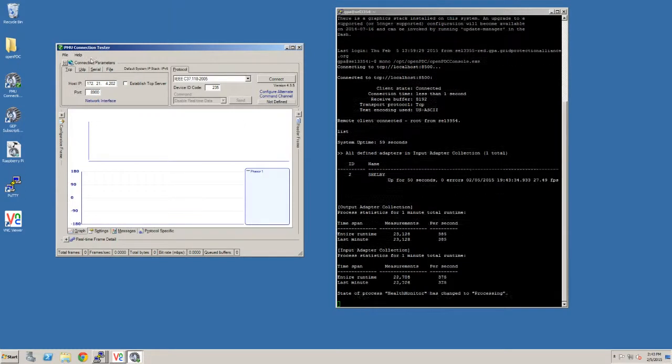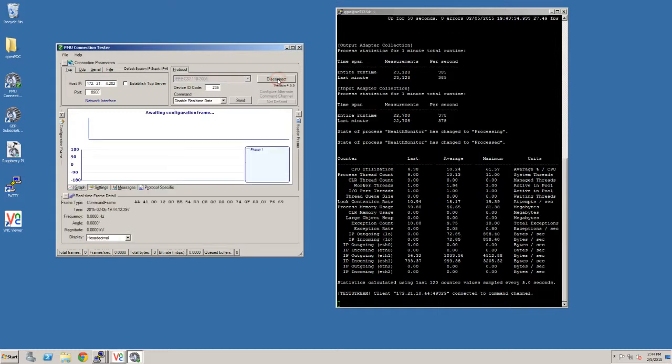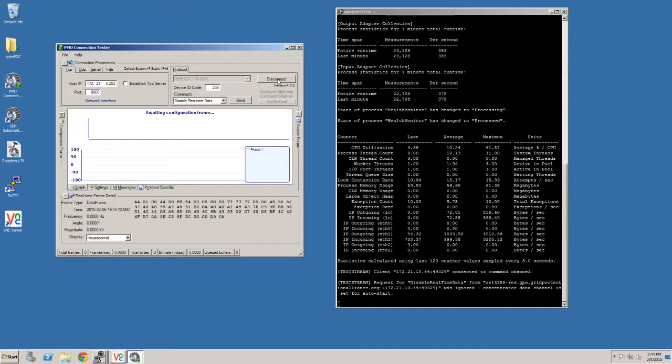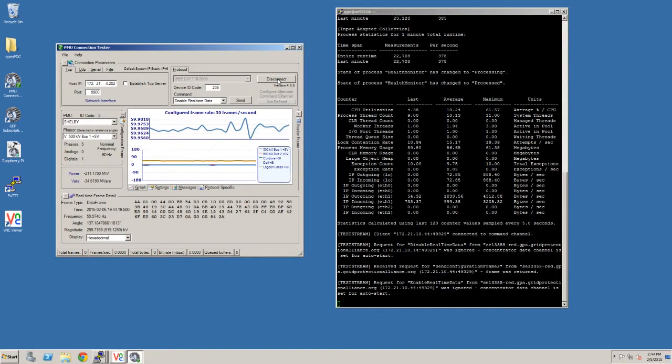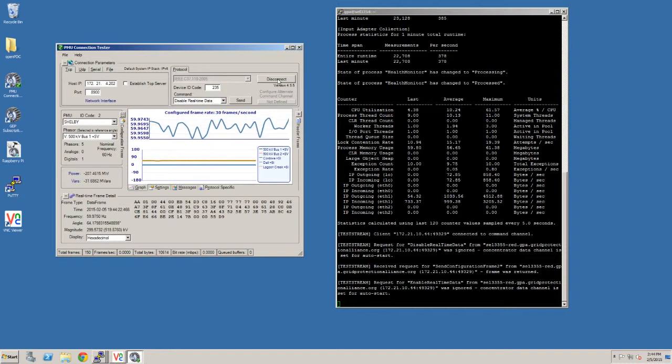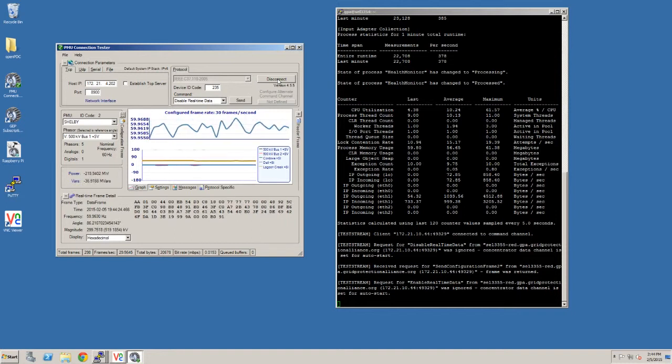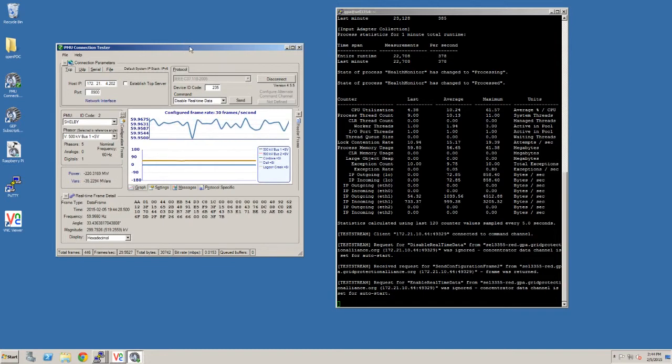Now let's try the PMU connection tester. Okay, now I'm going to type in the IP of that machine. It's actually on our right, 202. Okay, good. C37, port 8900, TCP, go. Yay, all right. So you can see on the screen how on the feedback from the open PDC, it saw a connection. And you can see that we're reporting C37.118 data directly from our Linux machine.